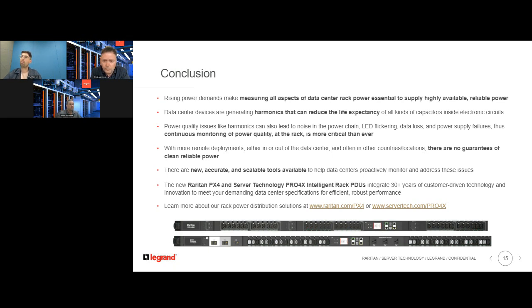So Sven, just to recap, because one of the follow-up questions is how do we predict the right kind of network load? Is the suggestion to actually analyze which are the data points that you care about and only collect those? Yes, that's the general way to do it. Don't submit all the raw data to your DCIM system, because it will get overloaded. And like I said earlier, there are so many data points you can measure with our PDU, but you really have to optimize it for your environment, for your facility. And this is where consulting comes in from both DCIM and also from us, the PDU vendor. And we can, of course, provide bandwidth information if we simulate a certain behavior of a PDU. That really depends on the use case. Okay.